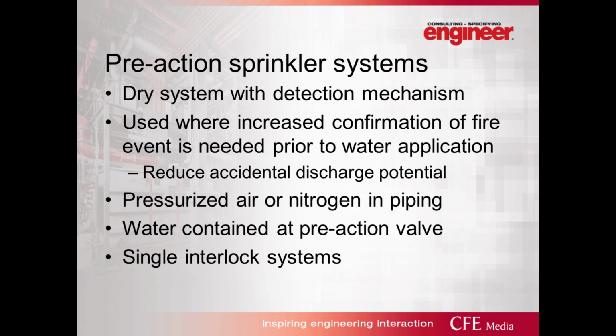Pre-action sprinkler systems are dry systems with an additional detection mechanism, and these are primarily used in areas where it's important to confirm that a fire event is actually occurring before you apply water to the area. You'll see the pre-action systems in areas that are protecting high-value storage items. You'll see them in data rooms where the application of water really is dependent on making sure that there's actually a fire occurring. Obviously, with wet systems and dry systems, if someone mechanically damages a sprinkler or something like that and accidentally activates it, you will get water flowing out.